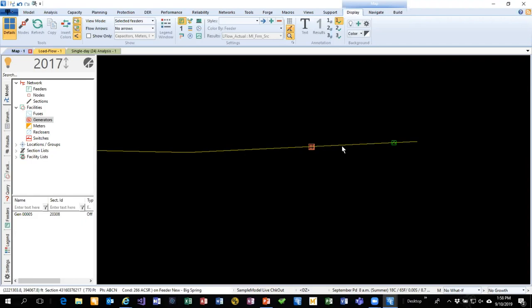If you're using aggregated, yes, because obviously that riser that goes up the apartment building, you will have, I guess, let's say 10 apartments on each floor. So if it's a 50 meter riser, the average height of it perhaps is 25 meters, and then you can apply all the aggregated load for all those customers at the end of that main. Yeah, that's the way I would recommend at the moment. Any more questions?